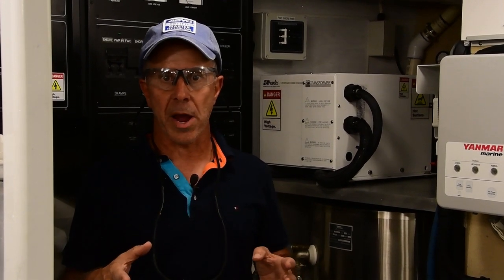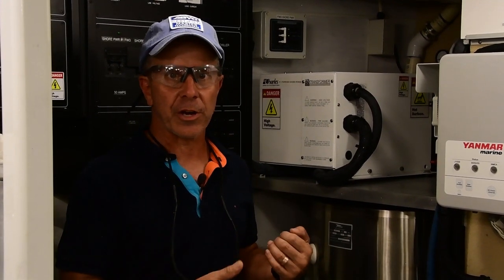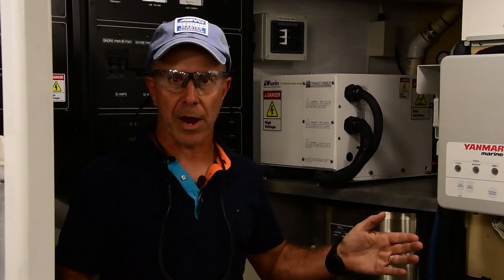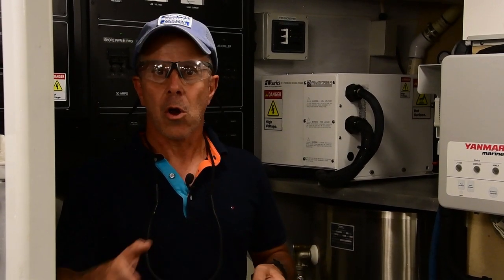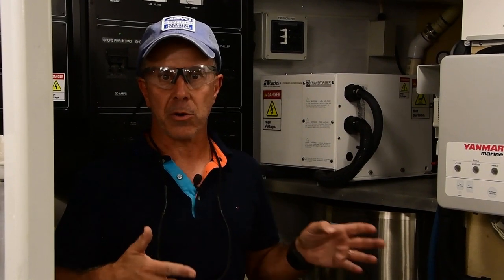The primary difference is the shield that exists, the metallic shield that is installed between the windings, the primary and secondary windings of the transformer. That shield prevents any arcing or otherwise inappropriate contact between those two windings in a variety of scenarios. And generally, when that transformer is installed, if it's installed as an isolation transformer, the shield is grounded to the shore ground. The chassis of the transformer is grounded to the boat's ground. If it's installed as a polarization transformer, all of the grounds are common: shore, shield, boat, and chassis. They're all connected together. If it's an ABYC compliant marine transformer, it'll meet those guidelines and it'll be the safest possible installation that you can have.